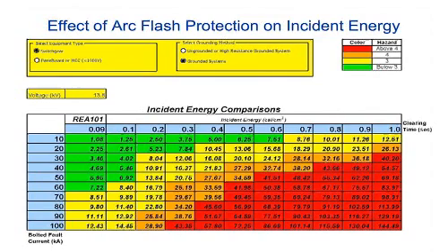So at 53 milliseconds, which is as fast as I can clear a fault with a 3-cycle breaker and an REA, you're in this range. That says that through 30 kA, I'm still at PPE level 2. You can see how dramatically this will start changing the way your workers can get in and out and do the work, correctly and very, very quickly. Okay, that's why it's very important.